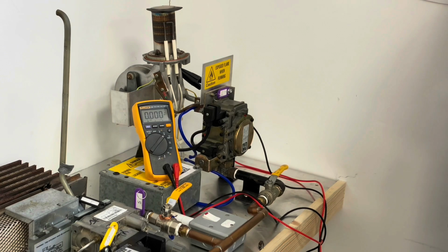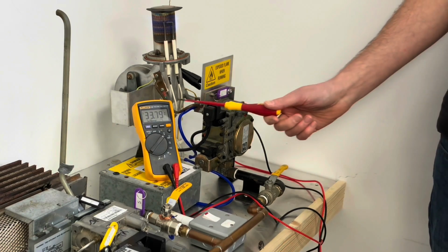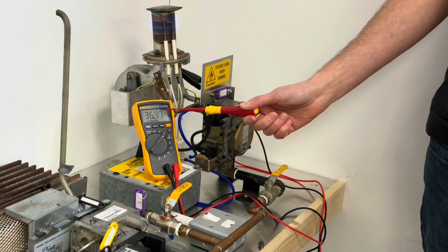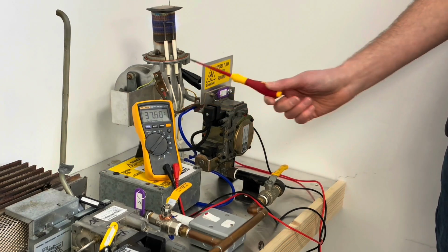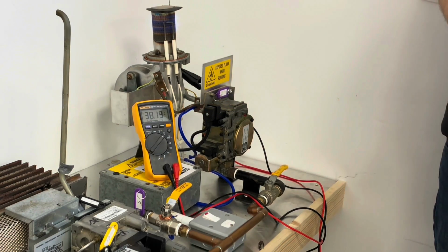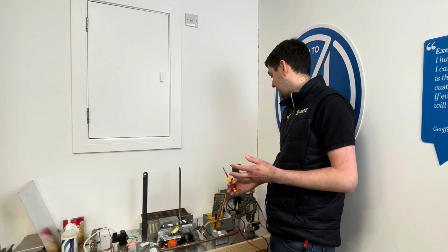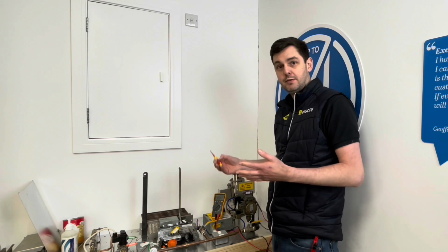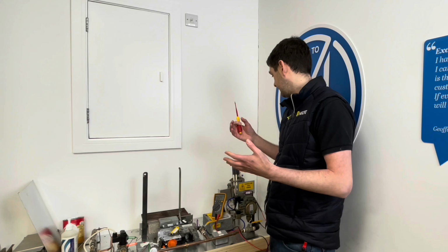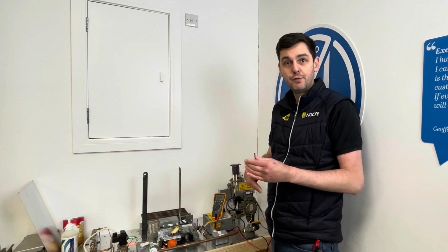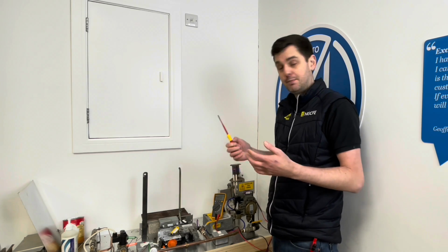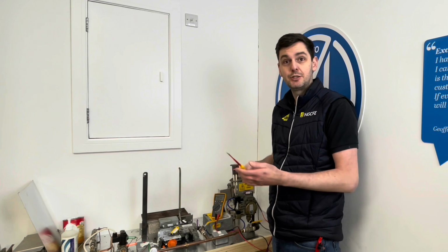Fan's purging, goes through its ignition sequence, and it's ignited. And now what we've got is a readable 35 volts DC current travelling back to the board. Now that's an indication that the flame's present and that the voltage AC is rectified through the flame, and that's how the board knows that a flame has been established.